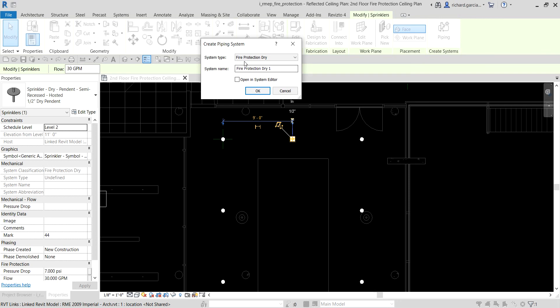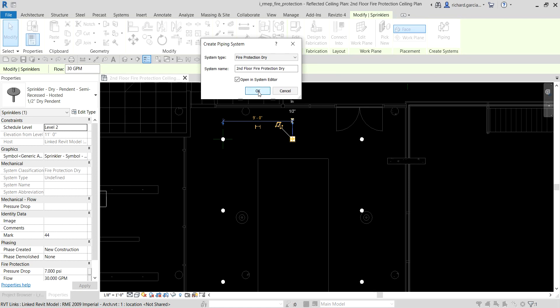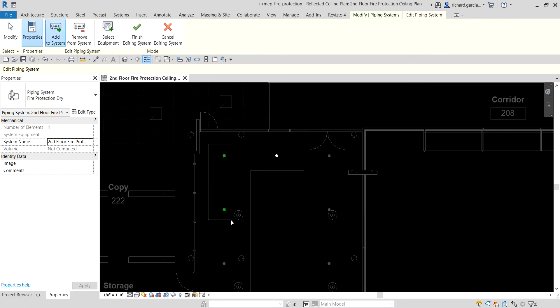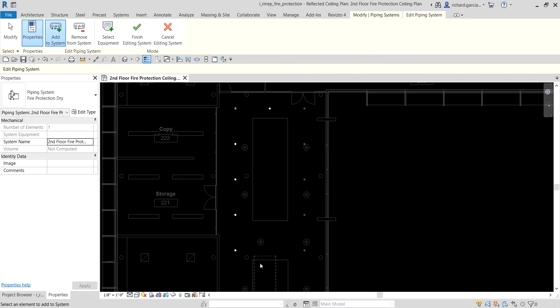You now have 'Fire Protection Dry' available. The connector for this sprinkler is a dry connector, so the system is dry. I'll name it 'Second Floor Fire Protection Dry,' then select Open in System Editor. Add to System is already selected, so I'll select all the sprinkler heads I want to add to the system, then click Finish.